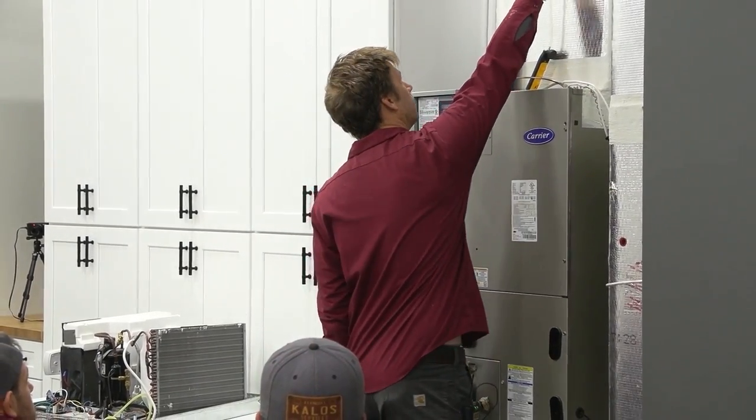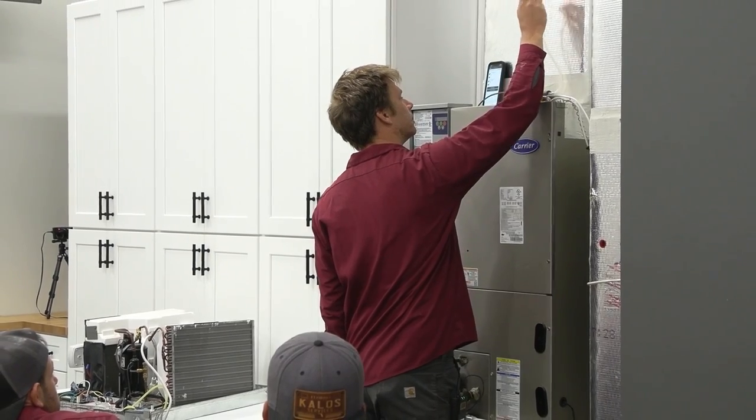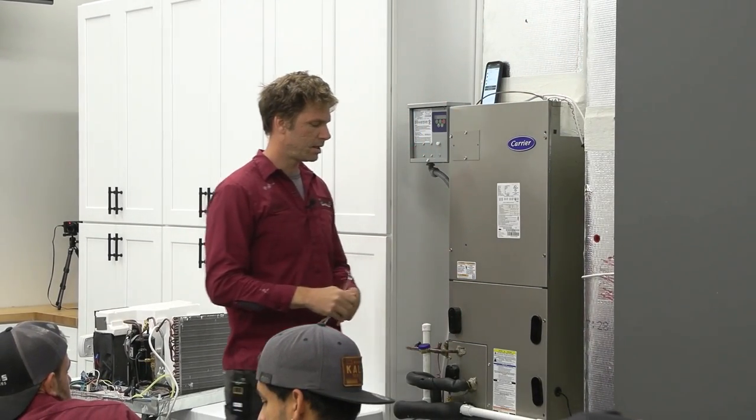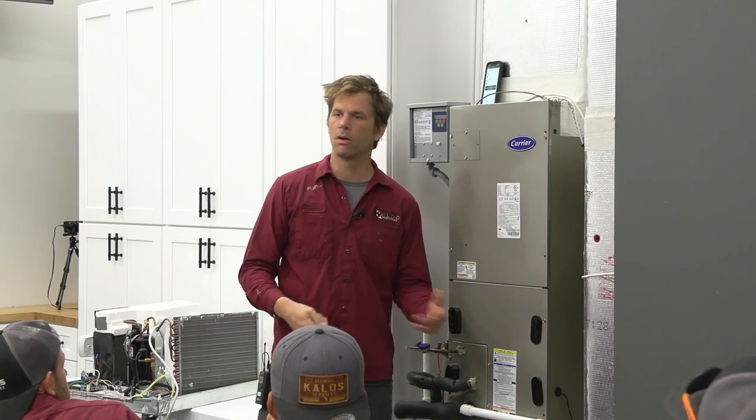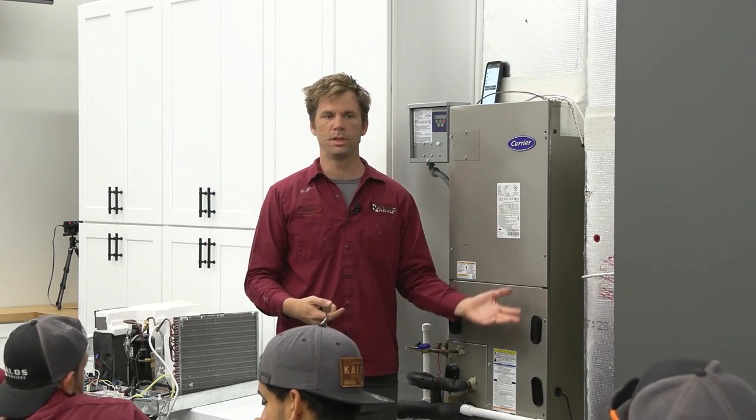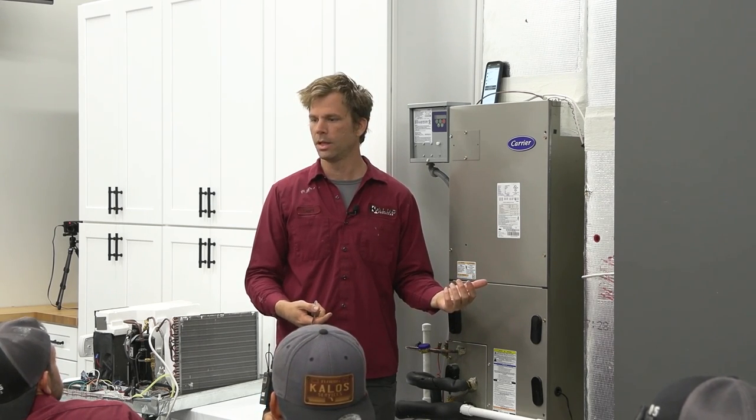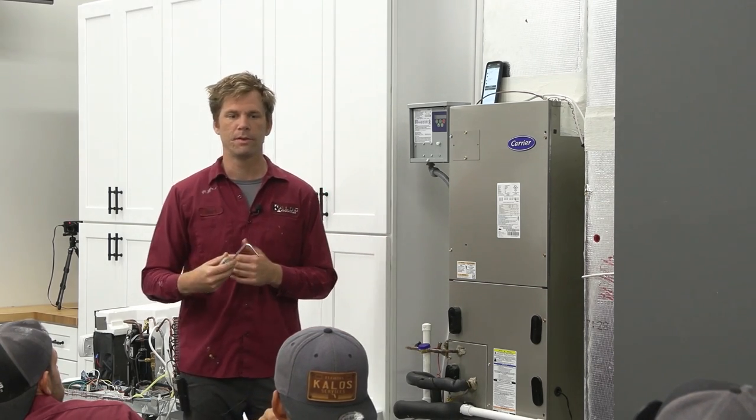I want to talk about using this in diagnostics. When you're using this in diagnostic, you sometimes have a situation where you are checking across your filter. So you do this test, pull your filter out and see what kind of a difference that filter's making. If you're wondering if the filter is really restrictive, if it's too restrictive, you can do that and see what kind of static pressure drop you have.